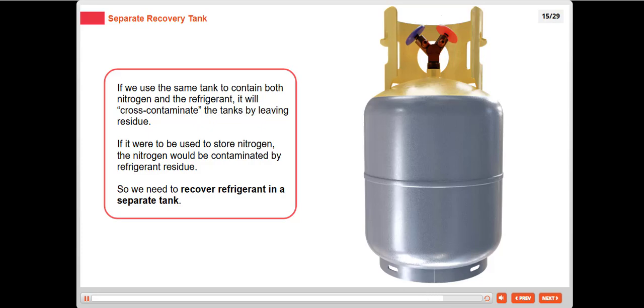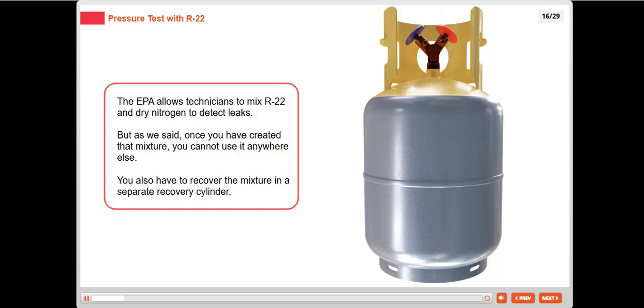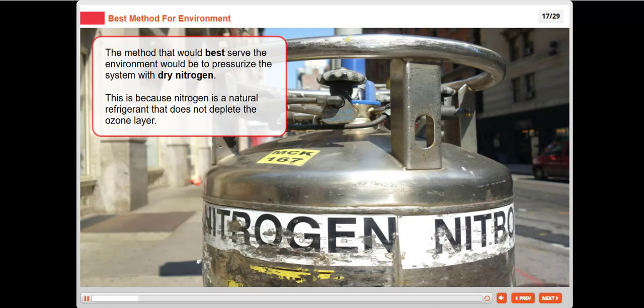The EPA allows technicians to mix R22 and dry nitrogen to detect leaks. But as we said, once you have created that mixture, you cannot use it anywhere else. You also have to recover the mixture in a separate recovery cylinder. The method that would best serve the environment would be to pressurize the system with dry nitrogen. This is because nitrogen is a natural refrigerant that does not deplete the ozone layer.